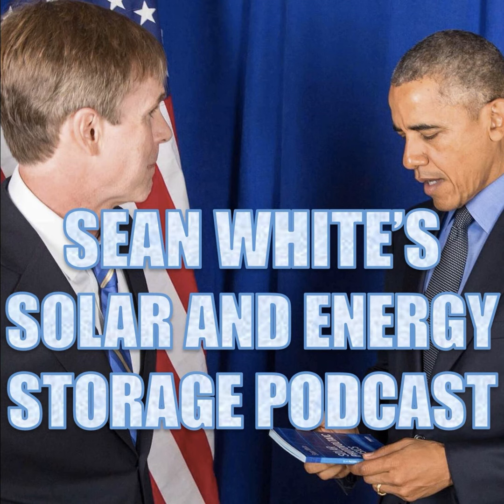And now let's talk about the C/2 rate. Sometimes we see that with lead acid batteries especially, and that would mean 1/2 C rate. So if you discharge your battery at a C/2 or a 1/2 C rate, that means you could discharge half of your battery in an hour. And this is not always what you could do. A lot of times what we're looking at is the amp hours at different C rates, because if you discharge a battery slower, you get more out of it, especially when you're talking about lead acid batteries. Lithium batteries are not as bad for losing energy when you discharge fast.